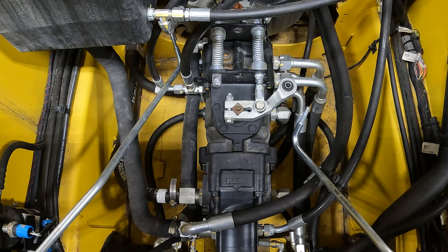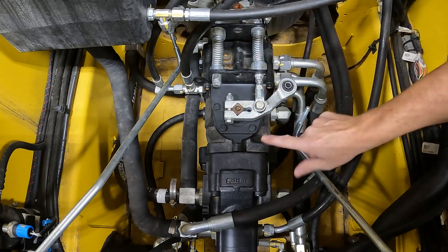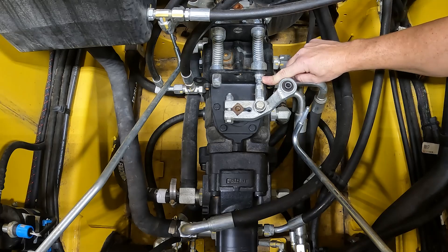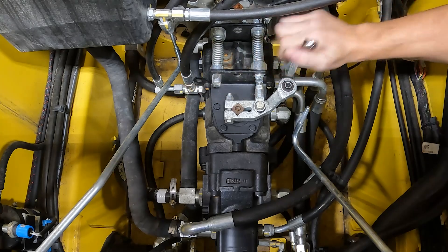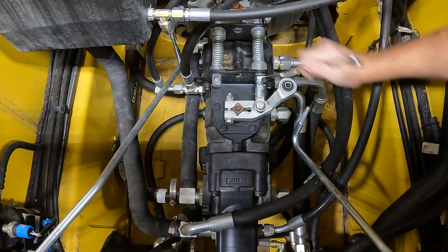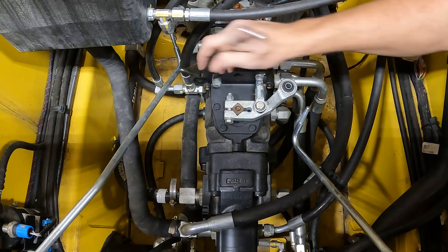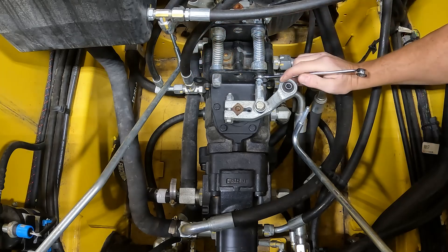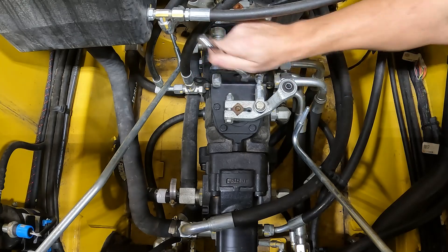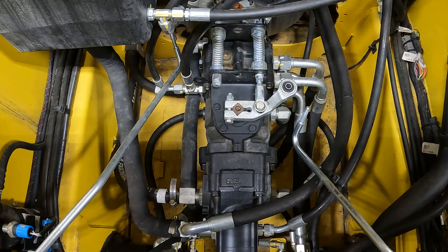Let me show you what an incorrectly set spring pack would look like. On the lever there are two jam nuts that hold the spring pack in place. I'm going to use the 9/16 open-ended wrench to make the spring pack too loose, creating movement in the spring pack — to show you how to neutralize it if you observe it out of adjustment. Tighten up that jam nut. This is a scenario where the spring pack is loose, not set correctly — it's not neutralizing the pump.